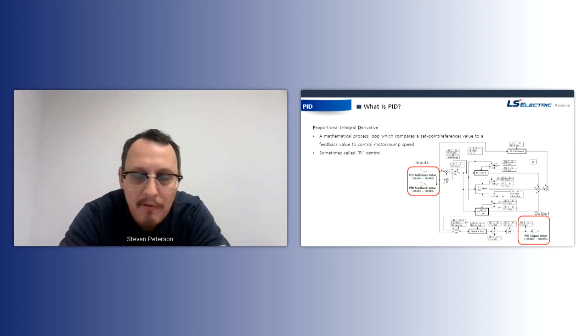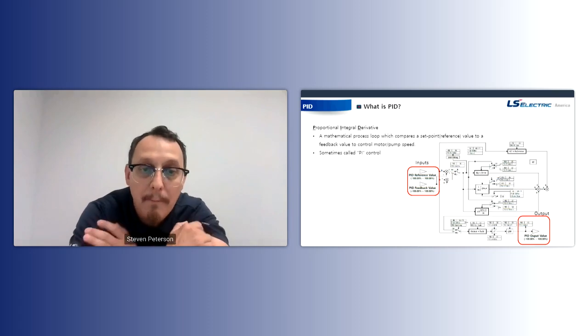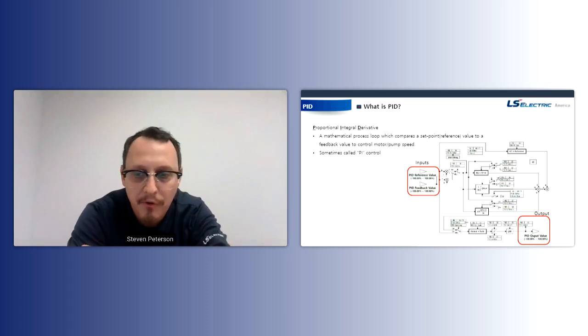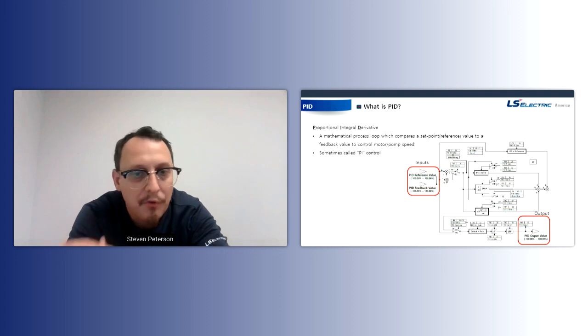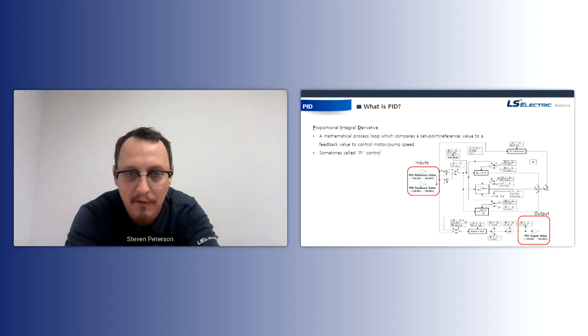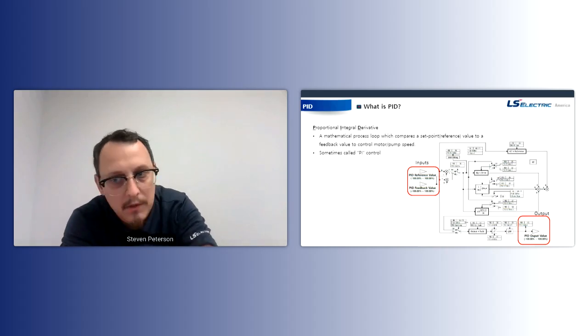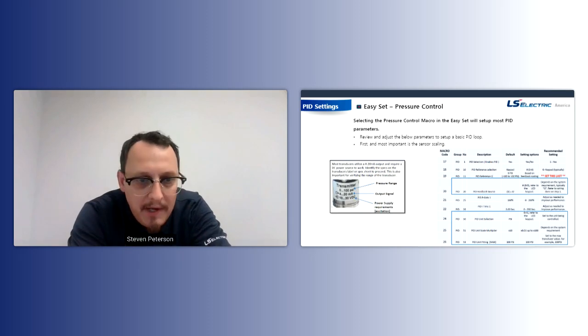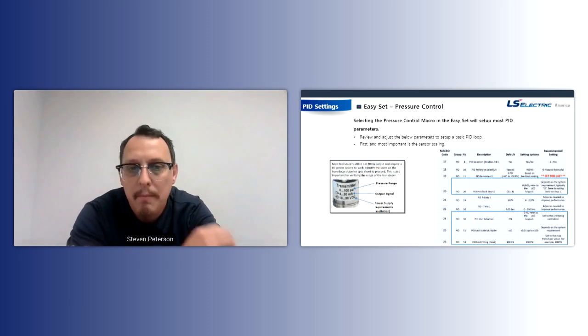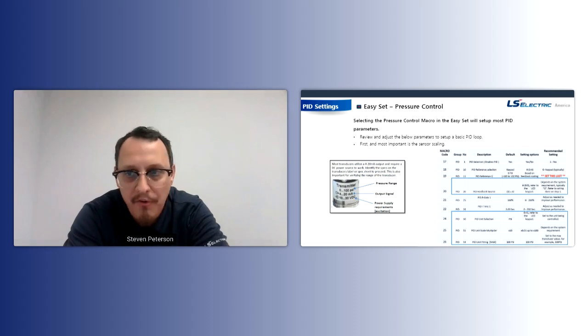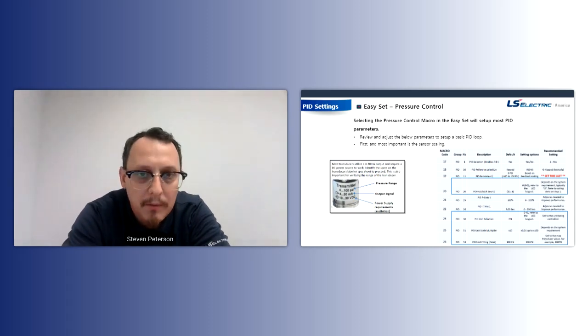So in regards to a VFD, that's really all the PID function is doing: comparing a set point to a feedback and regulating motor speed to get the two to match as close as possible, to meet demand, essentially. And we made it as easy as possible. We actually have a pressure control macro. So you power up your VFD, it says, hey, are you running pressure control? You select pressure control, and the drive actually guides you through everything you need to set up a PID loop.